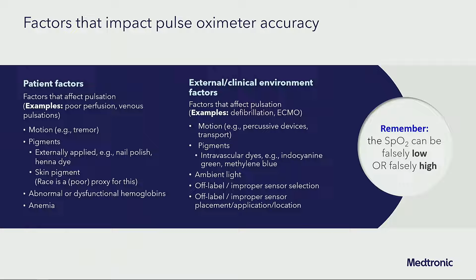External factors: anything that affects pulsation, so if you're defibrillating someone, if they're on ECMO, if they're getting PT on a bed that's shaking, all of that can affect the pulse oximeter. Pigments, again, can be patient pigment or the pigments that we give, so intravascular dyes. Methylene blue is a fun one in the ICU. Ambient light can affect the performance of the pulse oximeter. I've said this a few times and I'll hammer it home: if you are not using the sensor the way it's supposed to be used or in the place it's supposed to be used, that will affect the performance. There are forehead pulse oximeters, but if you take one that's meant to wrap around the finger and stick it on the forehead, that's a no-go.